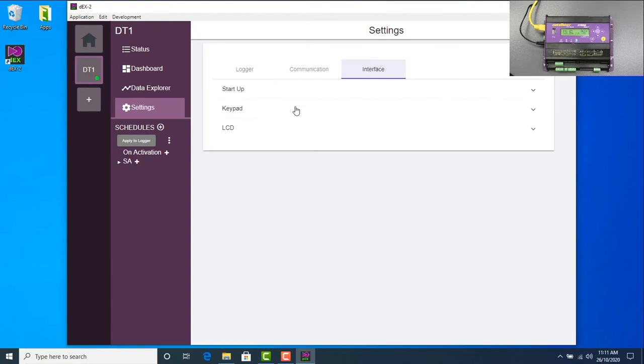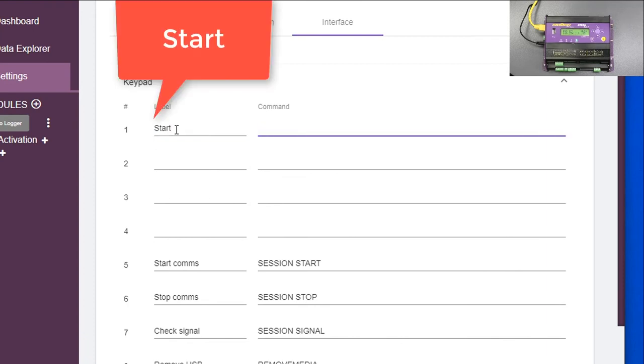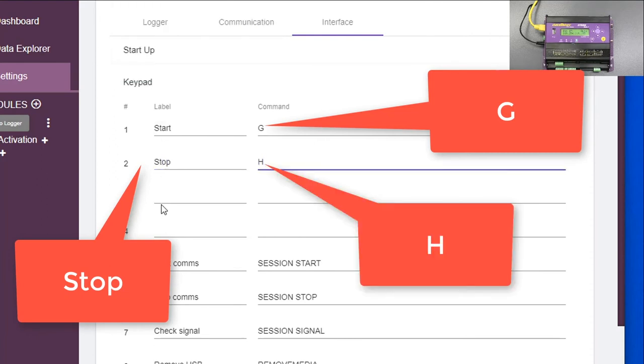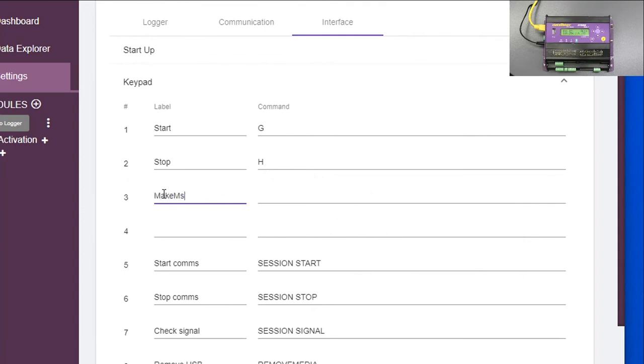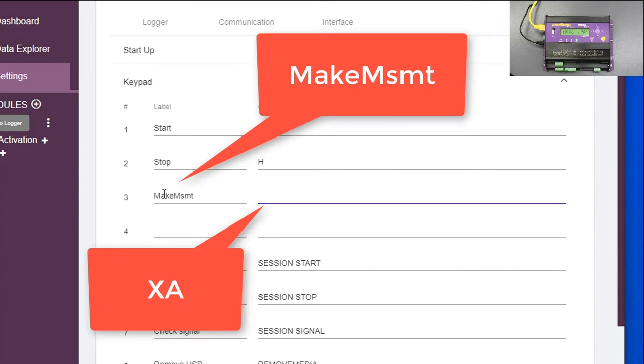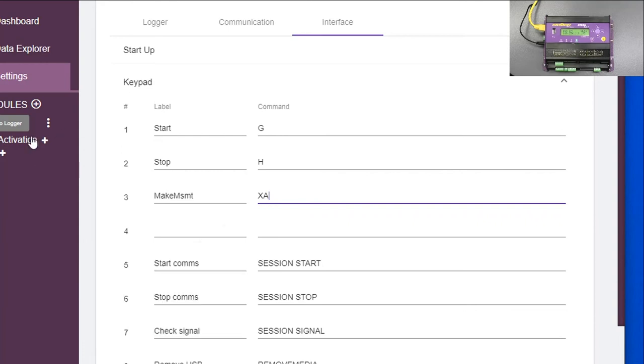The other thing we need to change or add, it's very useful, is there's a keypad. A number of keypad functions. It's worthwhile putting one here: start, and the command to start it is G. Stop, command to stop it is H. And usually make measurement. There's schedules in the name A, B, C, D, E, F, G, et cetera. We usually program that up with a single schedule. And if you want to cause when the logger has actually started to make a measurement instantly, execute XA will cause it to make a measurement straight away. These can be either uppercase or lowercase.